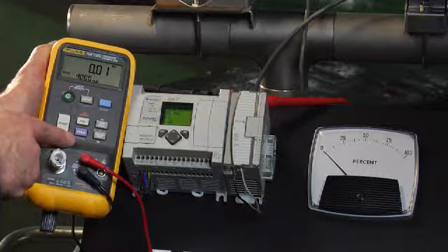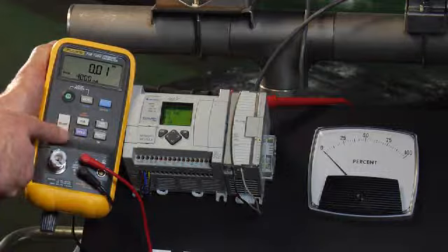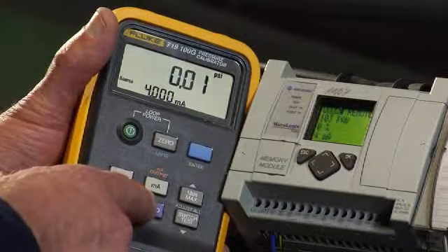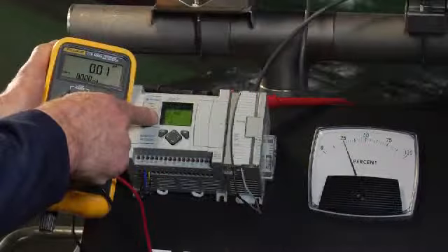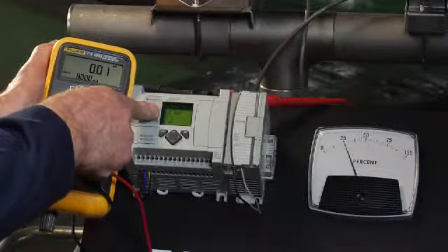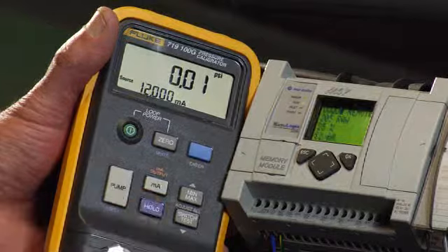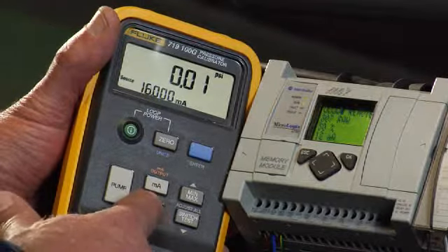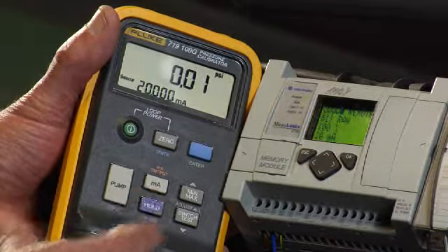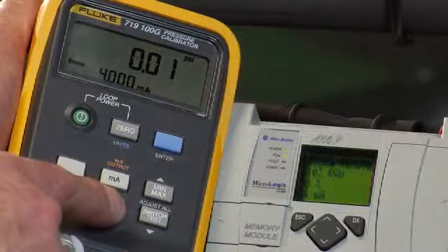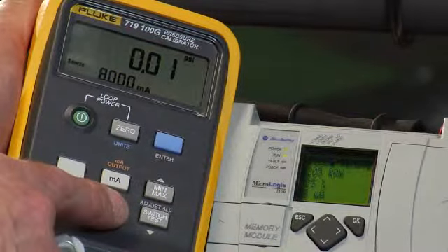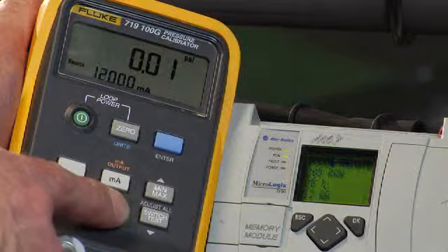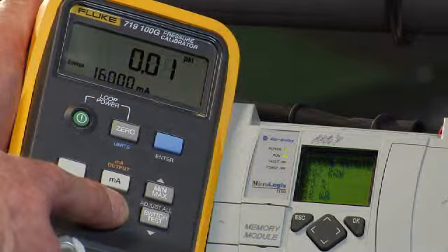Press the 25% step button to increment the output in 25% steps. You can see 4 milliamps, 8 milliamps on the indicator, and 25% on the PLC. Again, advance to 50%, 75%, and then 100%. To make small adjustments in milliamps, use the up and down arrows to change the output in small increments.